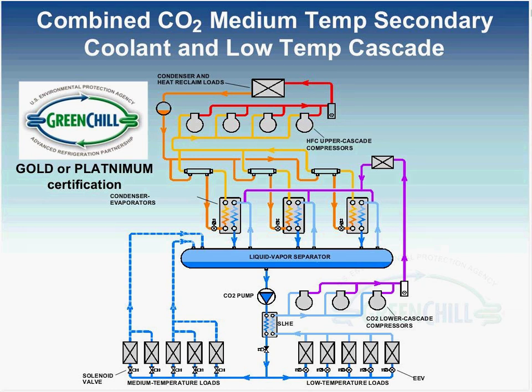A tremendous reduction in refrigerant charge, and you can go to platinum. We've done a couple of these systems achieve platinum certification. And again, whenever you go with this low charge platinum, you have to be very concerned what you do with your condenser and heat reclaim loads on that upper cascade or top side system. That greatly affects the overall refrigerant charge because you have reduced the charge so much. So the microchannel condensers and strategically locating those condensers close to the top side rack is important.